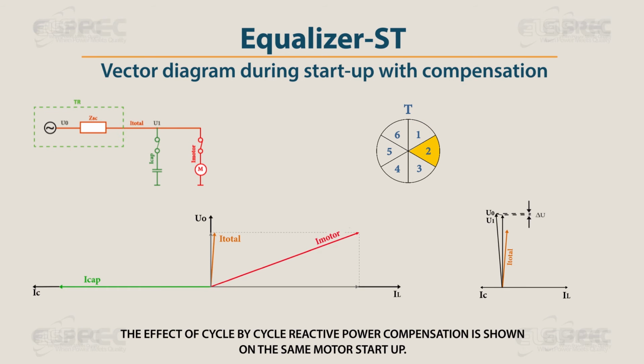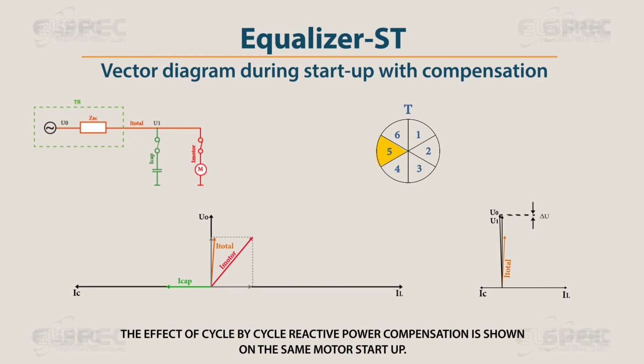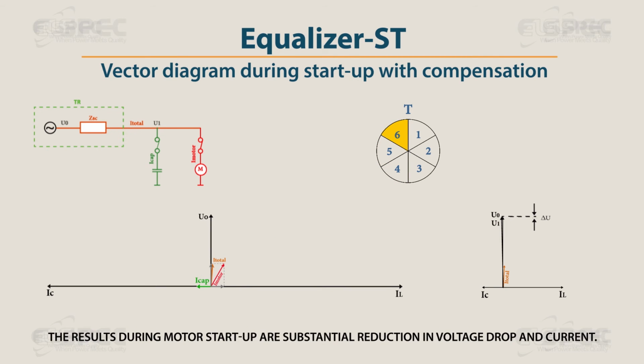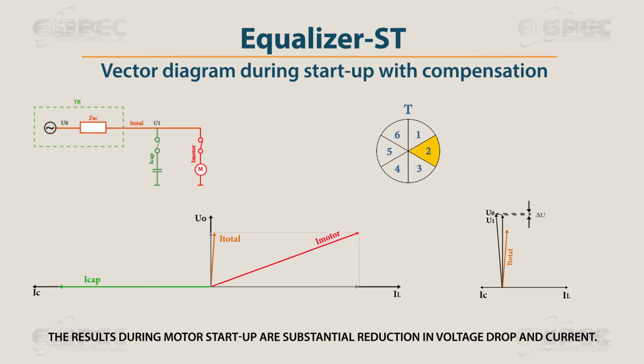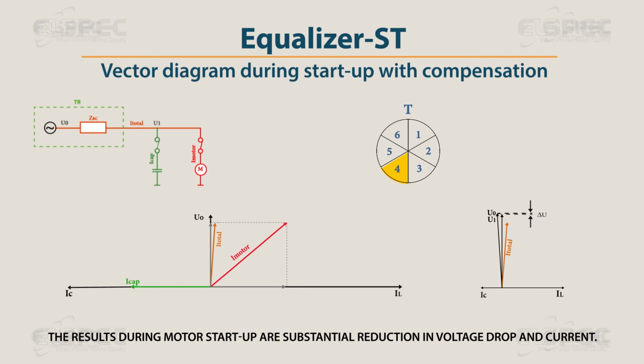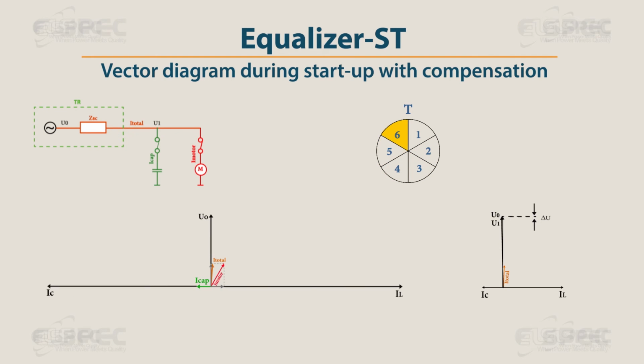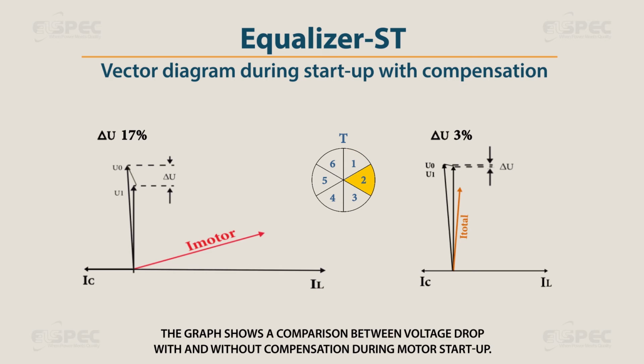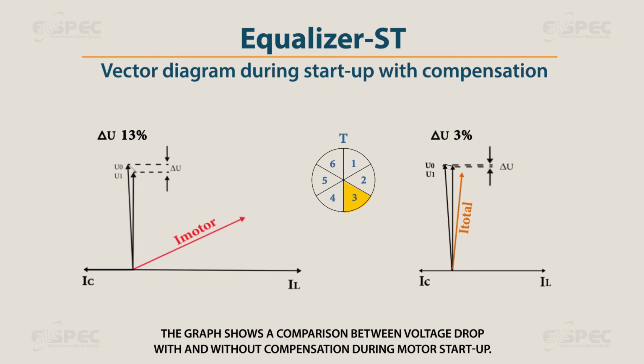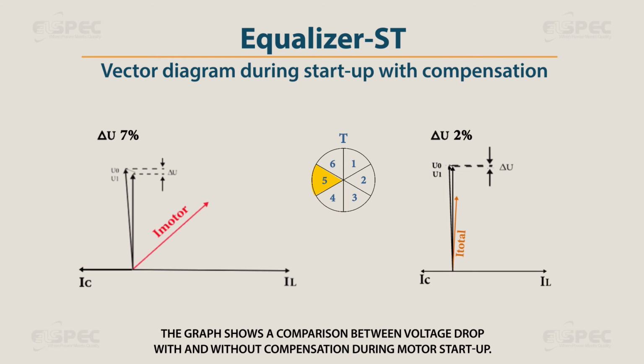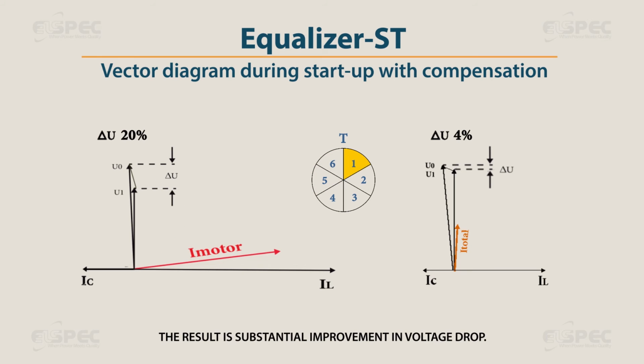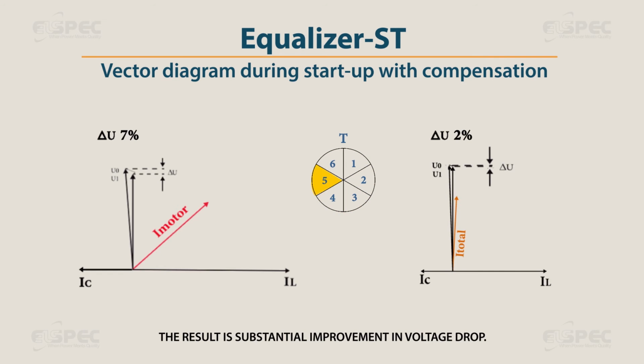The effect of cycle-by-cycle reactive power compensation is shown on the same motor startup. The results during motor startup are a substantial reduction in voltage drop and current. The graph shows a comparison between voltage drop with and without compensation during motor startup. The result is a substantial improvement in voltage drop.